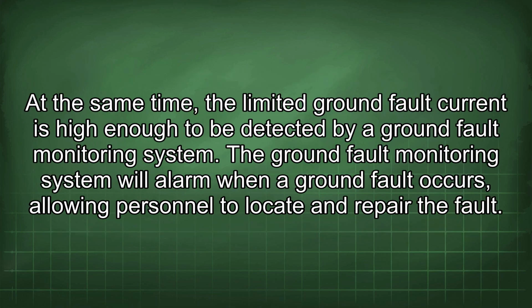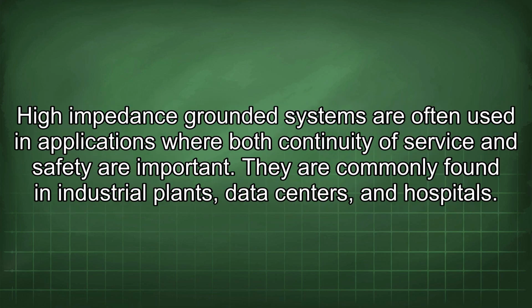At the same time, the limited ground fault current is high enough to be detected by a ground fault monitoring system. The ground fault monitoring system will alarm when a ground fault occurs, allowing personnel to locate and repair the fault. High impedance grounded systems are often used in applications where both continuity of service and safety are important. They are commonly found in industrial plants, data centers, and hospitals.